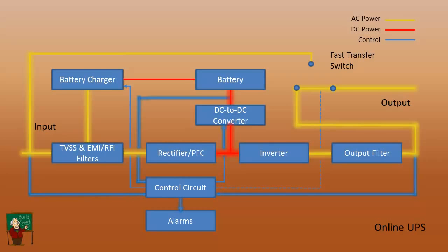Now we'll go back to the normal condition on the UPS, and we'll look at another possible fault condition that could occur with the UPS. And that would be if we lose output from the inverter or the output filter. You see, as that goes away, that will set an alarm. The control circuit detects that and flips the transfer switch so that now the UPS is no longer in the circuit and the output comes directly from the input.